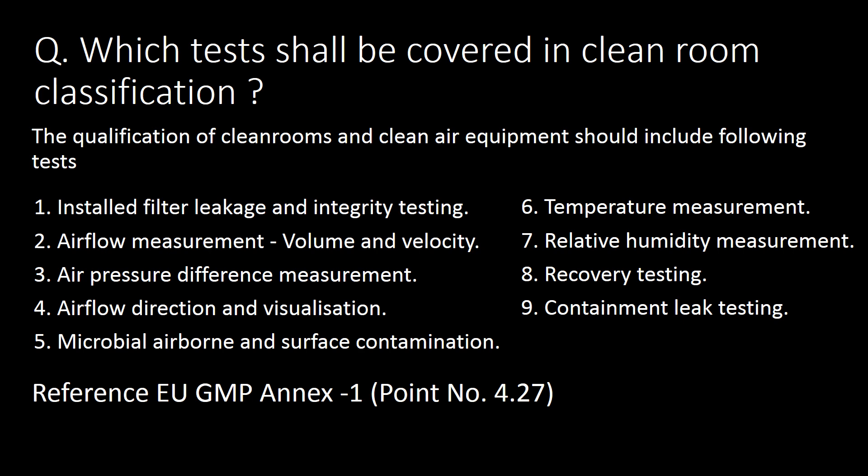Which tests shall be covered in clean room classification? The qualification of clean rooms and clean air equipment should include the following tests: 1. Installed filter leakage and integrity testing; 2. Airflow measurement; 3. Air pressure difference measurement; 4. Airflow direction and visualization; 5. Microbial airborne and surface contamination; 6. Temperature measurement; 7. Relative humidity measurement; 8. Recovery testing; 9. Containment leak testing. Reference: EU GMP Annex 1, Point No. 4.27.